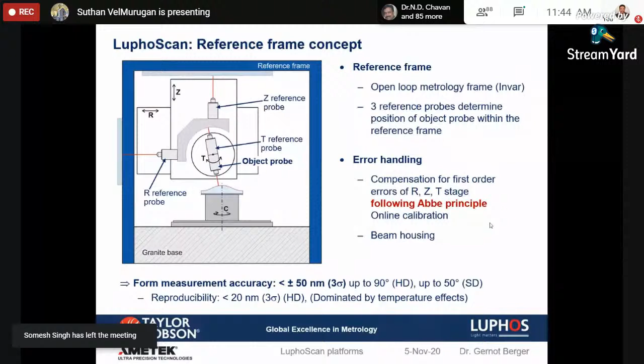So for each and every axis, the X-axis, the Z-axis, and the probe rotation, the scale is fitted in the same plane as the axis movement. That is why it is more accurate. In addition to that, the axis frame is made up of Invar material, which you will definitely know. It is a very stable material against temperature and the environment. With any temperature change, the thermal expansion of Invar is very, very minimal, which is negligible. That is why we use that material for all the axis movement frames. So these are a few reasons why this machine produces high precision results.